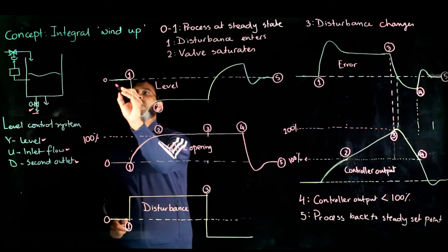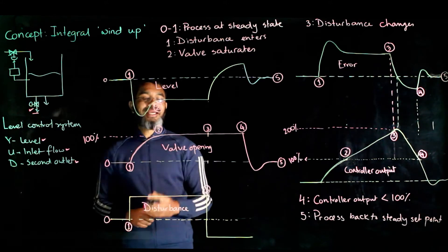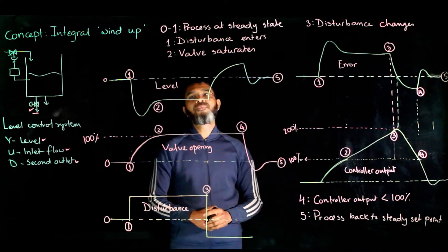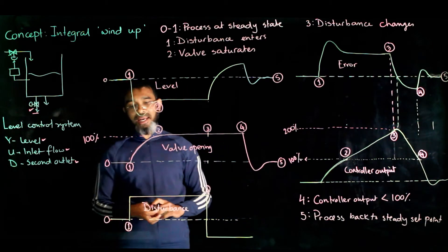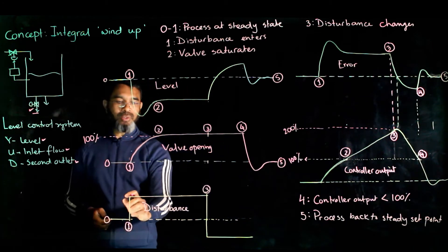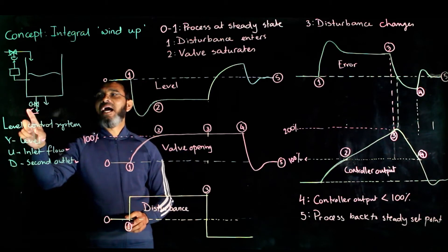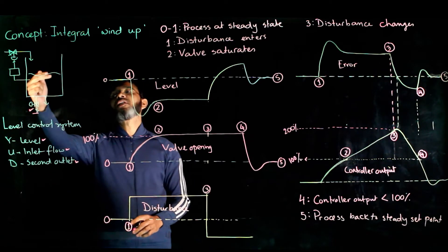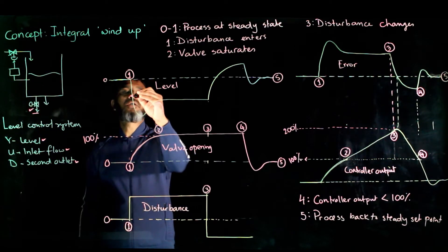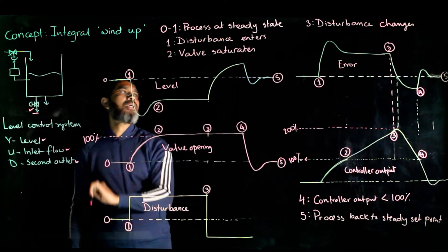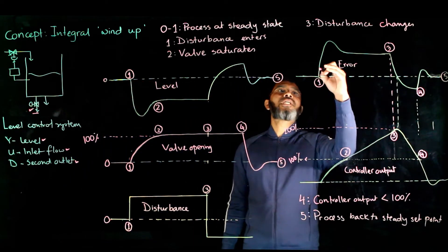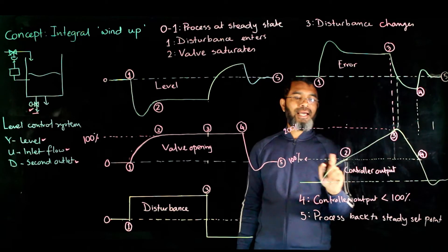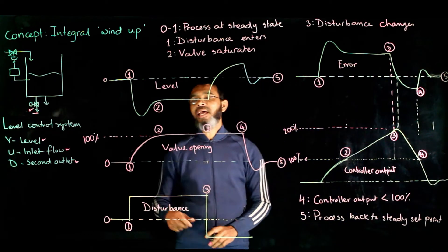At instant 0, everything has a steady value. From 0 to 1, the level, the valve opening, the disturbance, and error all have steady values. At instant 1, the disturbance enters the process — the second outlet is increased, causing the level to start decreasing. As the level decreases, the error signal keeps increasing and the controller starts calculating a control action, so the valve begins to open.